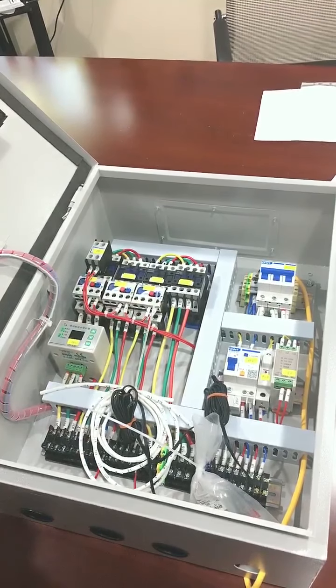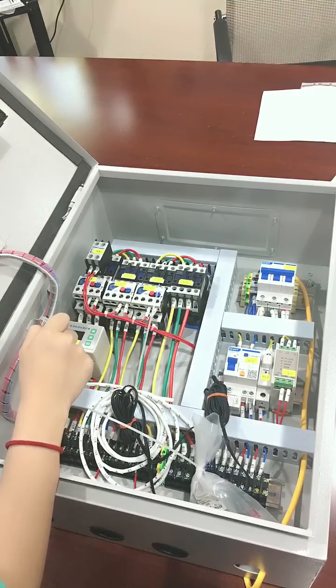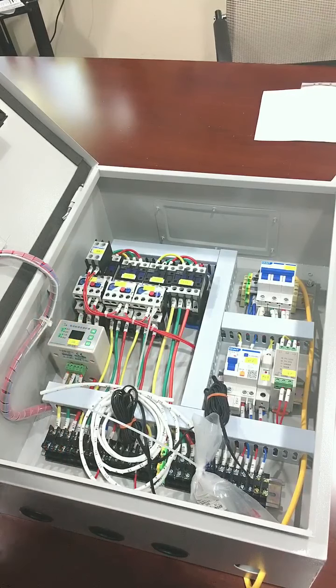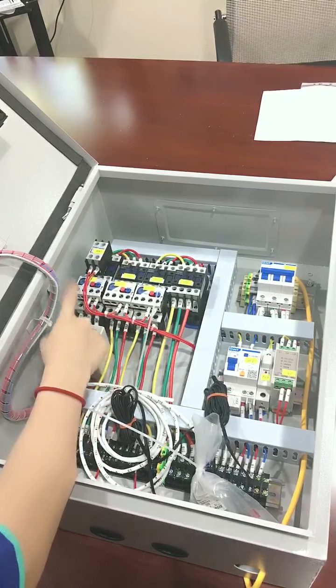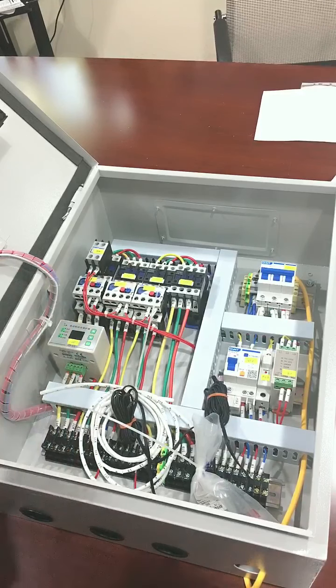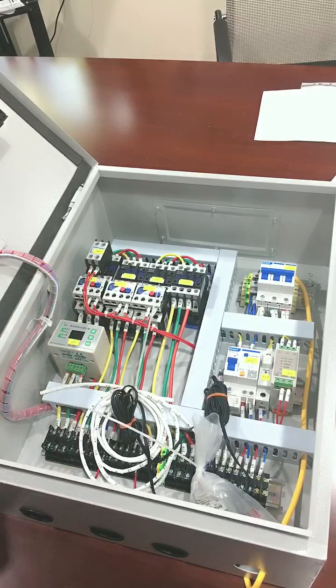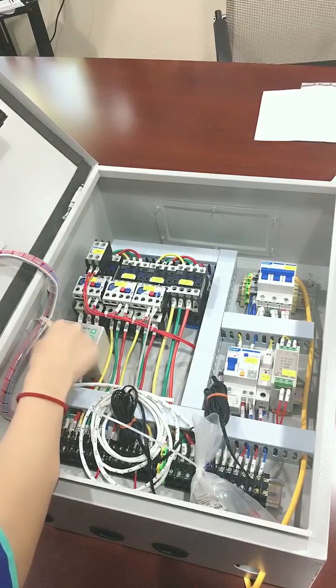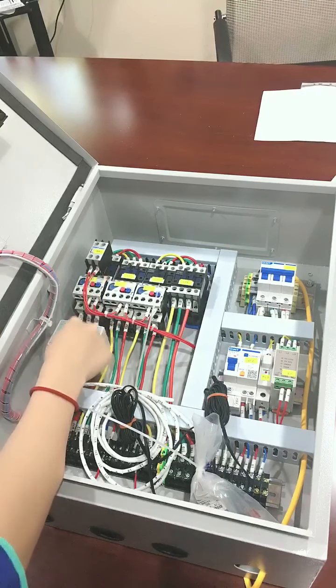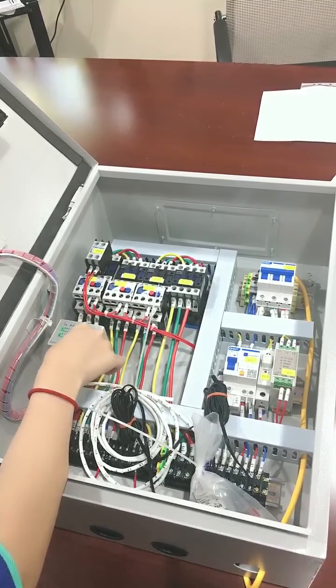As we know, the compressor is the heart of the refrigeration system. Here we add an additional part for protecting the compressor motor. This is the motor protector for the compressor. There are several functions in the motor protector. The first one is current overload. The second one is electric supply lack of phase, and the third is electric delay and so on. Our control box is focused on more safety and higher reliability of working for the cold room.